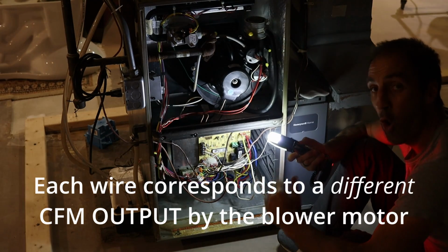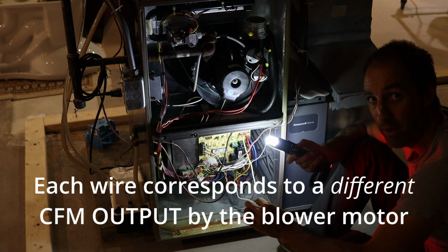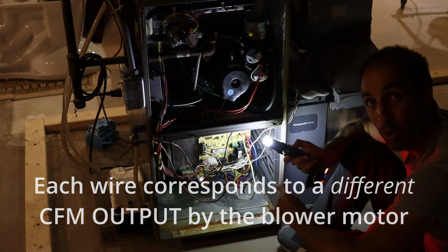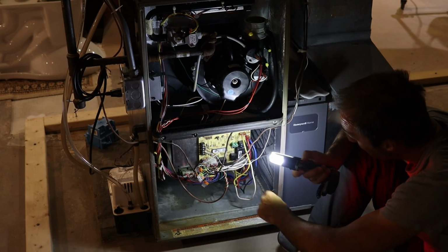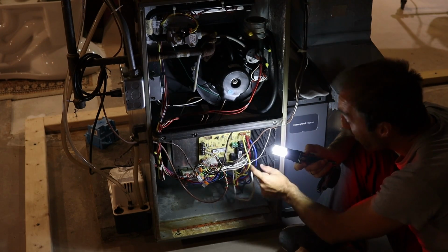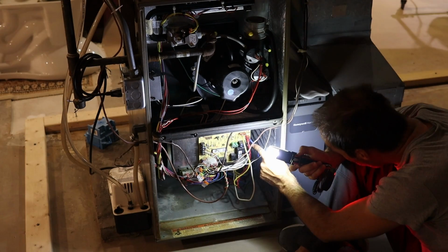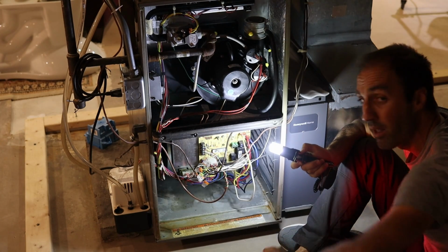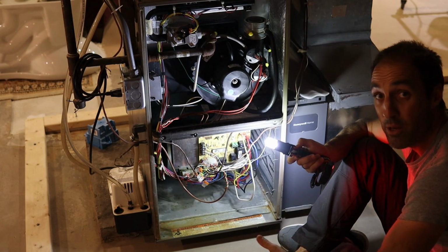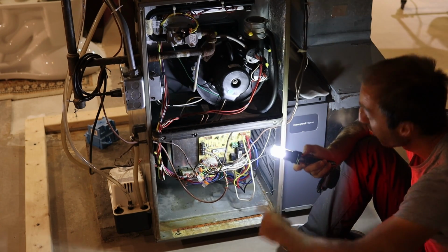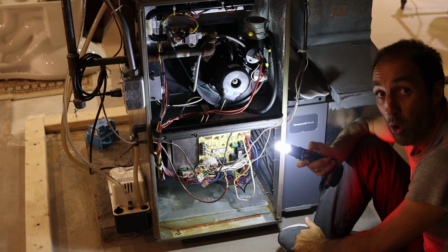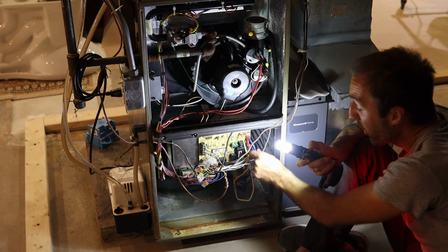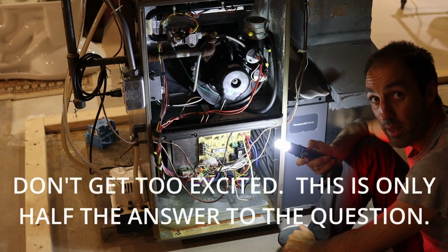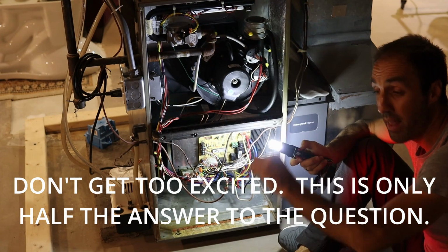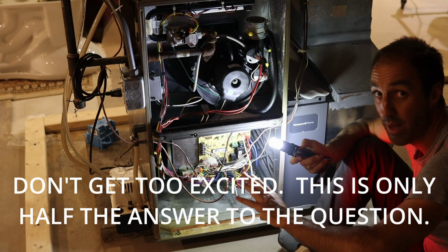You need to know what speed tap your blower motor is on, and you do that by coming in here and seeing what each is hooked up to. So I've got blue for cool and black for heating. Then you need to go into the manual to see how many CFMs your blower motor will push on that speed tap. Okay, so you got that? Let's hang on to that, put that on the side, and move on to something else.